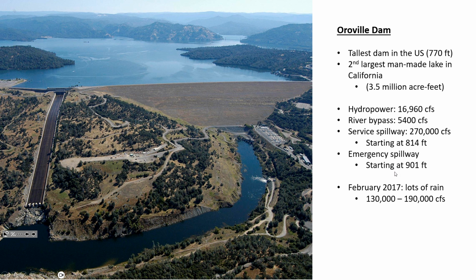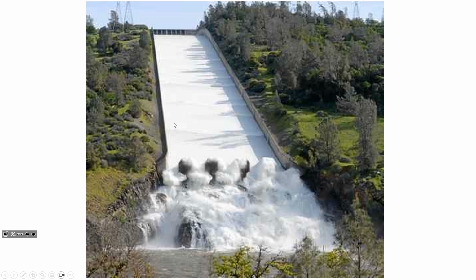So they had an incident back in 2017 where it was very wet in February. A lot of rain came all at once, and there was about 130,000 to 190,000 CFS of water that needed to be released. And so that's more than can go through the power plant. That's more than can go through the bypass. And so once you're having all the water possible go through both of those, they need to send some of the water down the emergency spillway. And it had been a while since conditions were that wet so quickly in Northern California. So the spillway hadn't been used in a while. And this is what it looks like under normal circumstances.